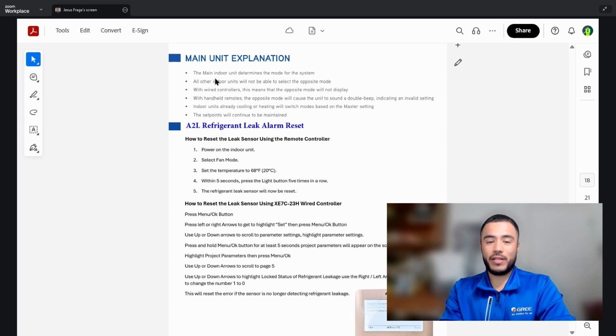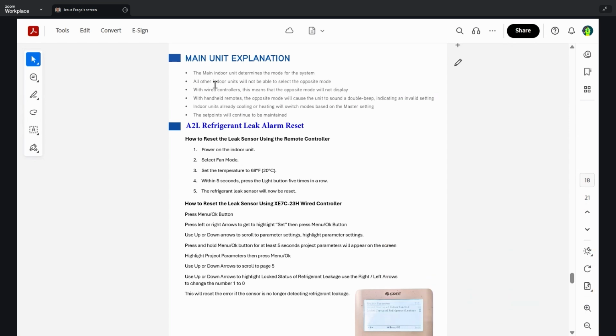That main indoor unit is what controls the mode from heating to cooling. So if you go to a controller and you try to change mode from heating to cooling and it doesn't give you the option, we know that that's a subordinate controller.